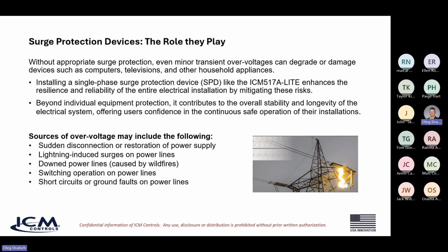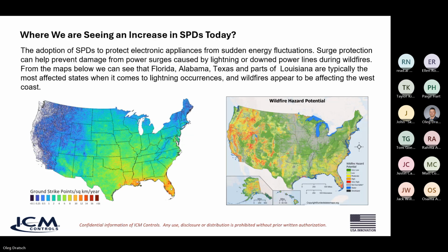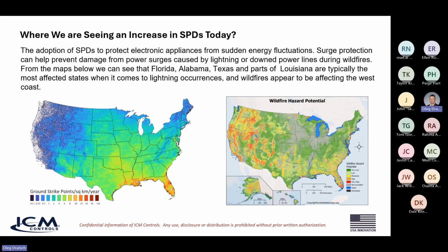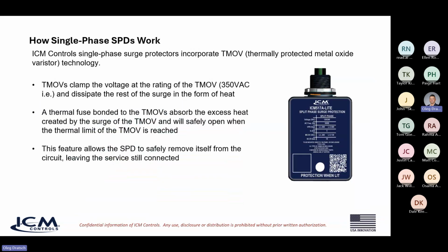So this device that we'll get into in a second, and you see on this slide right here, the amount of lightning strikes and wildfires and all these sorts of events that we hear about on the news all the time can all contribute to surge issues that you would need a device to protect from. And so with that, we've developed the ICM517A-Lite. Inside of this device are thermal metal oxide varistors, that's TMOVs. When a surge is sensed, they dissipate that surge in the form of heat. These TMOVs, and there are 6 of them, we'll show them on a coming slide, but essentially it is a low-cost insurance policy for your HVAC units, your furnaces, any type of appliance, washers, dryers. This is going to protect them.